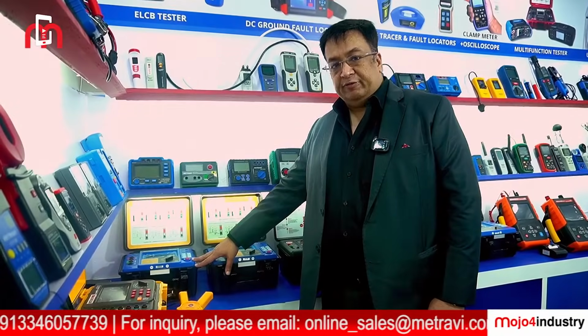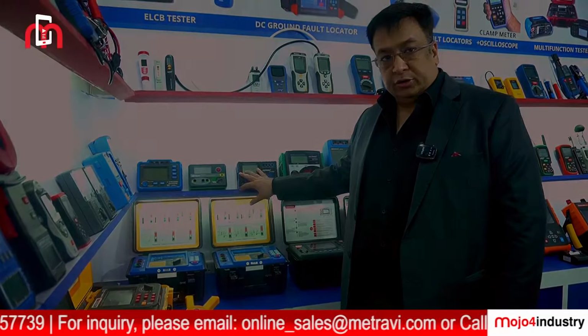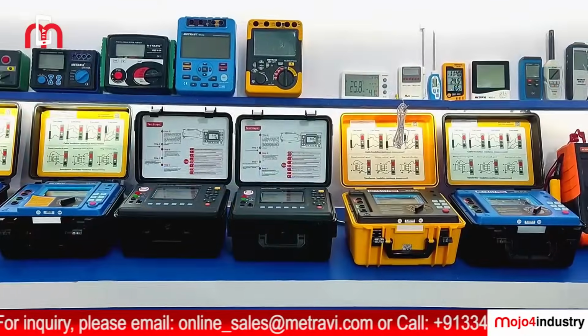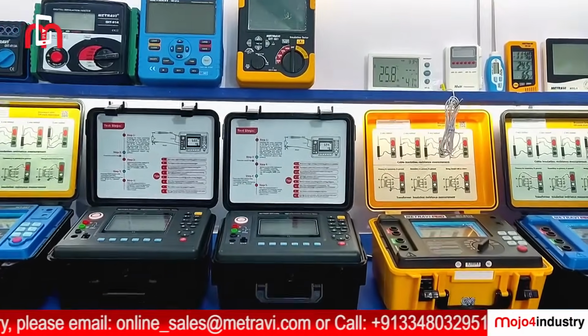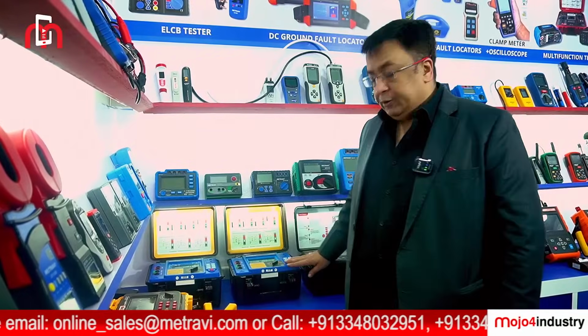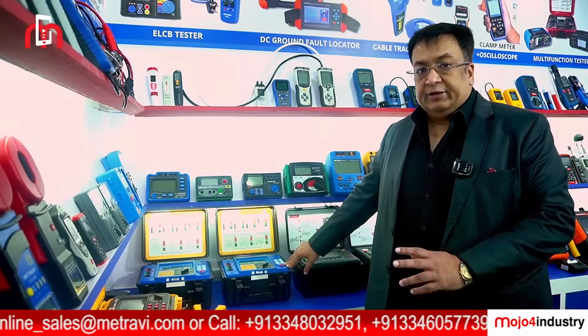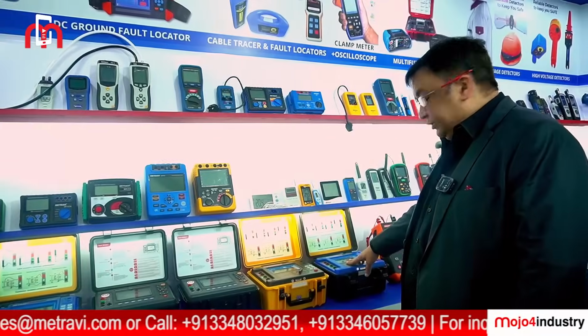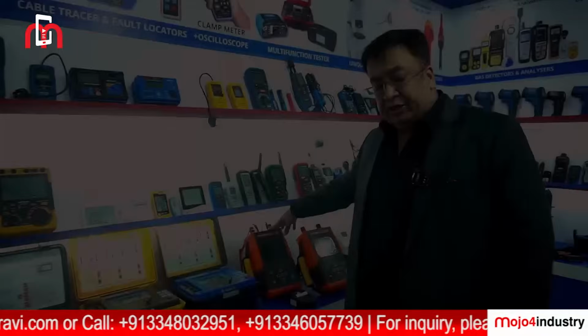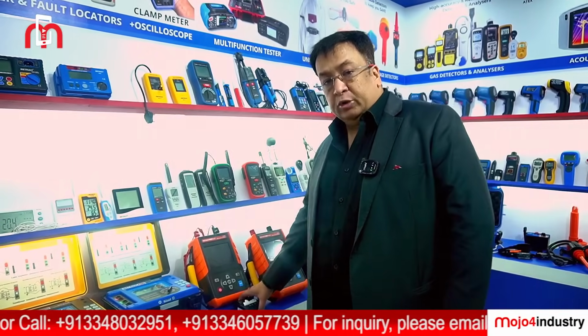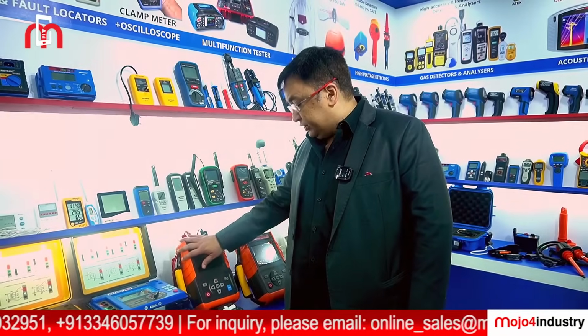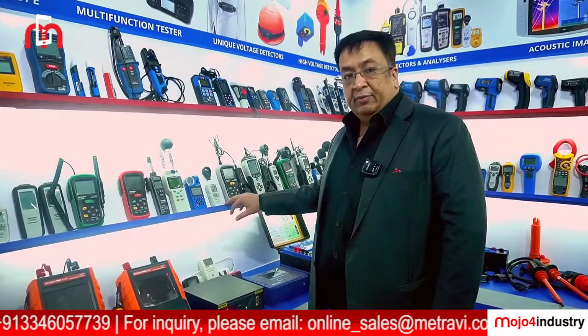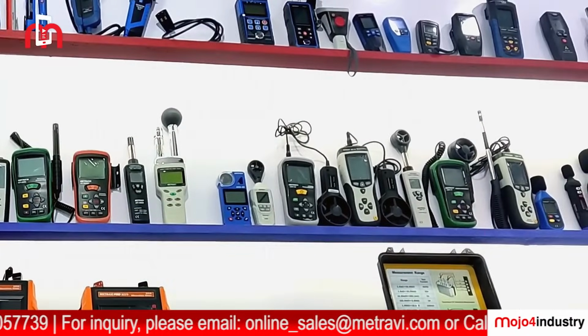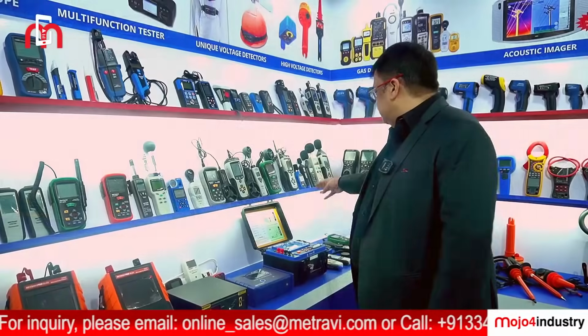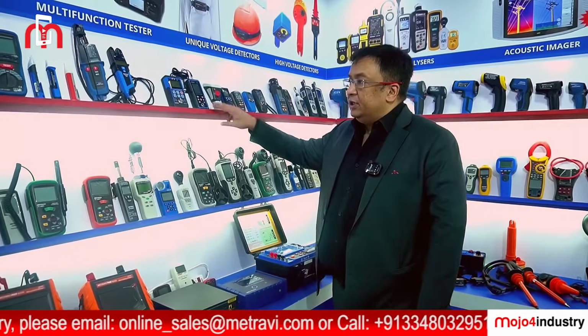We have insulation testers from 5 kV to 15 kV and for low voltages also. The special feature in this is you can program any voltage from 10 volts to, say, 5000 volts or 10,000 volts or 14,000 volts. For example, if you want to test at 550 volts, even that can be programmed in these instruments. This is a 15 kV insulation tester. Now we have the micro-ohm meter with a test current of 100 ampere and 220 ampere. This has wireless printers. So you take a test and you take a printout on the printers associated with this particular instrument. These are the environmental testers, from anemometers to heat index meters to sound level meters. You have coating thickness gauges and ultrasonic thickness gauges.